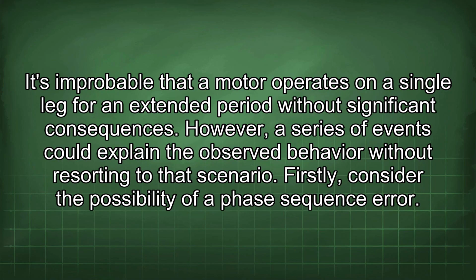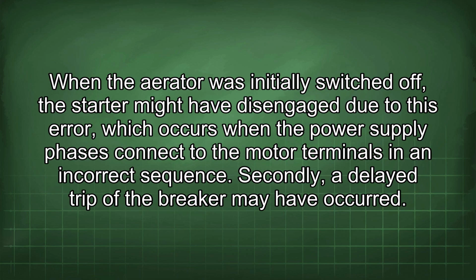It's improbable that a motor operates on a single leg for an extended period without significant consequences. However, a series of events could explain the observed behavior without resorting to that scenario. Firstly, consider the possibility of a phase sequence error. When the aerator was initially switched off, the starter might have disengaged due to this error, which occurs when the power supply phases connect to the motor terminals in an incorrect sequence.